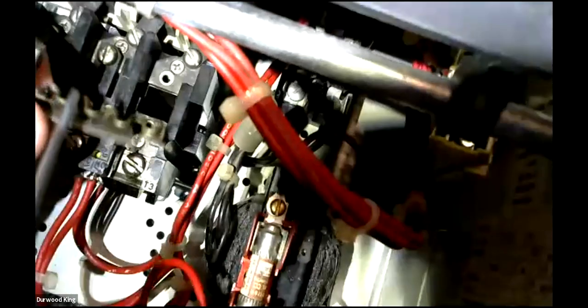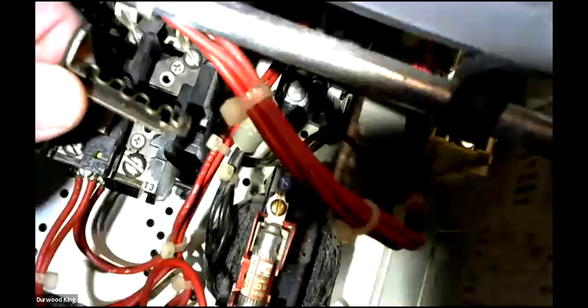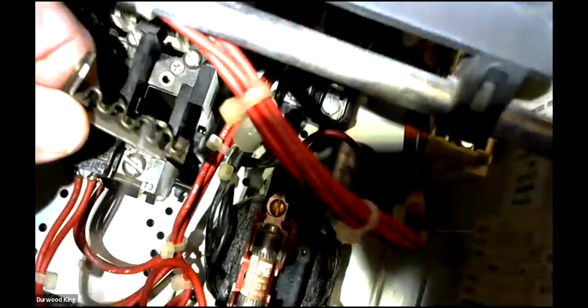So if you look down in there, you see that hole in there? Yeah. That's where that heater element goes down in there. So it senses motor current. If it gets too hot, what it does is it actually bends. And when it bends in there, it flexes. It's going to trip a mechanism in there. And when it trips a mechanism, here's what's going to happen.